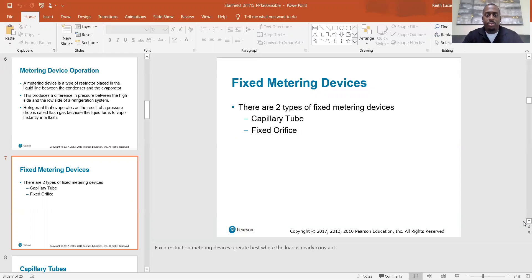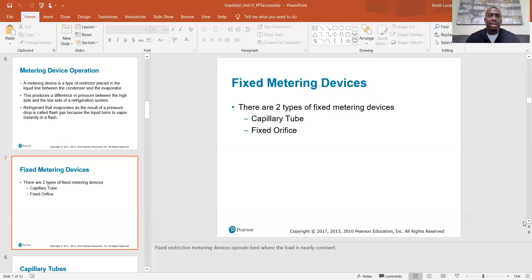There are two types of fixed metering devices: capillary tube and fixed orifice — also called piston or flowrator. Fixed restriction metering devices operate best where the load is nearly constant. In applications where the load doesn't change much, fixed metering devices work fine. But if load is constantly changing, a modulating metering device may be preferred, and those decisions are made by the manufacturer, not the technician.